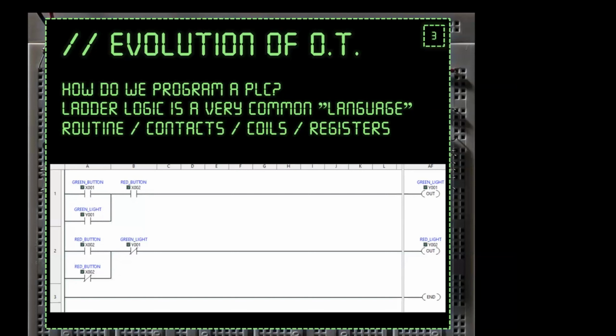It gives us the ability to assign addresses. If you look at the top left, you see X001 — that's an address tied to a physical input on one of those input cards. On the right you can see outs, which are coils tied to the Y addresses, the output cards. So basic logic here says: if somebody presses the button connected to X001, send power through. And if the red button is already pressed, we roll across that contact as well, sending power out to our green light.